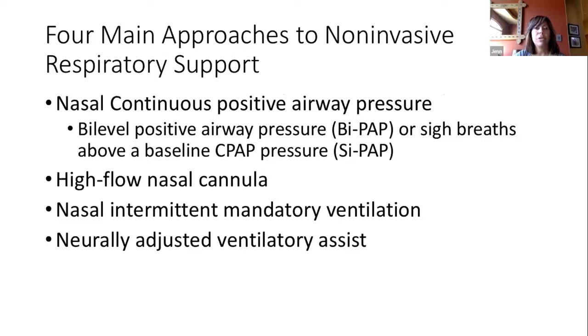So there are 4 main approaches to non-invasive respiratory support. Nasal continuous positive airway pressure, and that can further be broken down. You can deliver just plain CPAP, or like BiPAP or SiPAP, which adds a slightly higher peak inspiratory pressure with a rate to your CPAP. Then there's high flow nasal cannula, which has really come into favor over the last 10-ish years. And then nasal intermittent mandatory ventilation. So this is your NIPPV, your high frequency oscillatory ventilation, or jet ventilation via the cannula, which is currently sort of coming into favor and being used in different NICUs around the US. And then neurally adjusted vent assist, or NAVA.